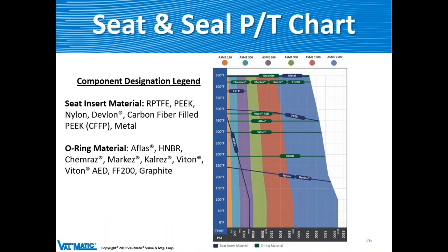Beyond the ANSI pressure rating, the soft and plastic parts inside the valve must also match the application. Seat material options include reinforced PTFE, PEEK, nylon, Devlon, and carbon-fiber-filled PEEK rated up to about 580°F, plus metal seats. O-ring materials available include AFLAS, Chemraz, Markez, Kalrez, Viton, and other special materials, as well as graphite for higher temperatures. We can source virtually any O-ring material required for a given application.